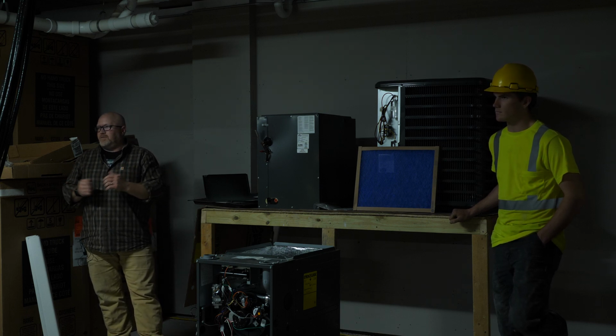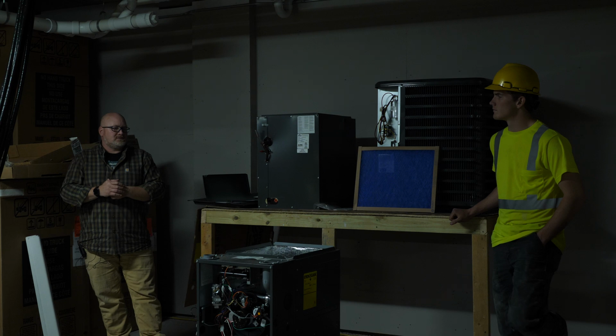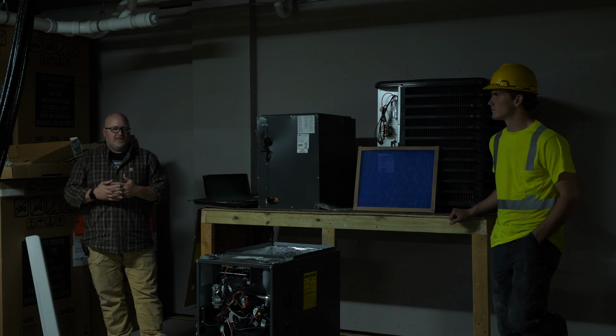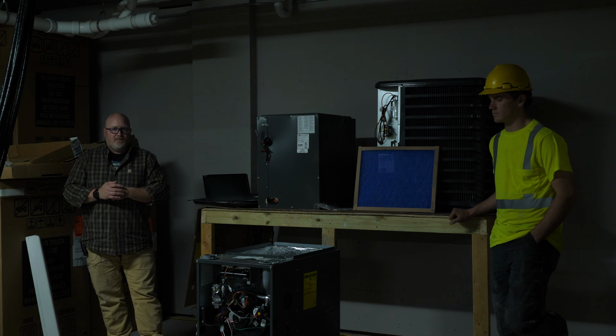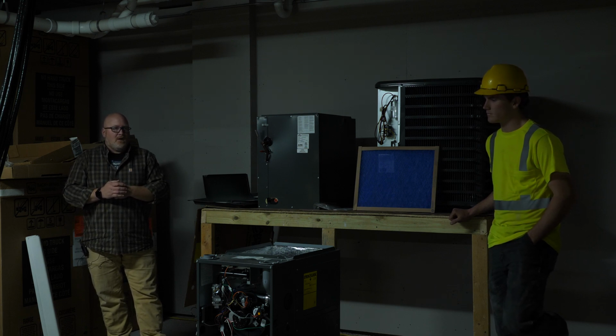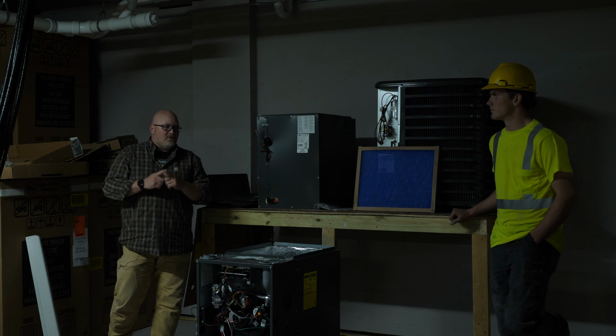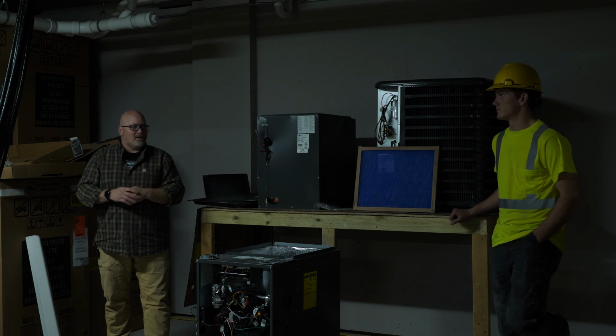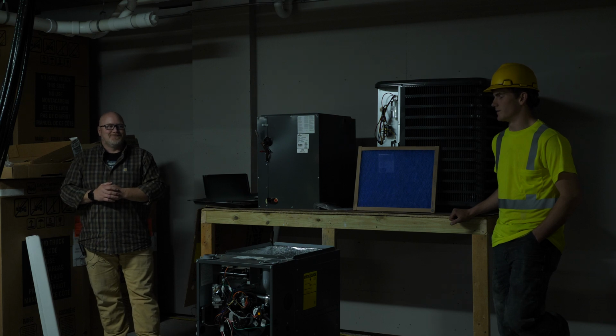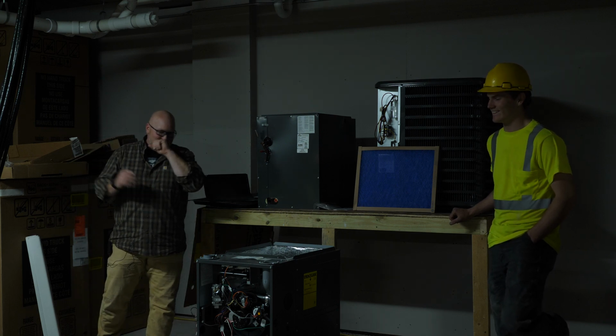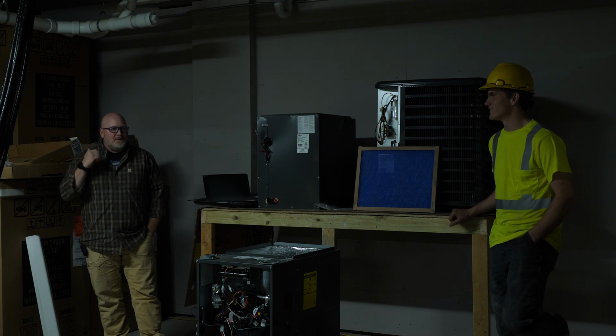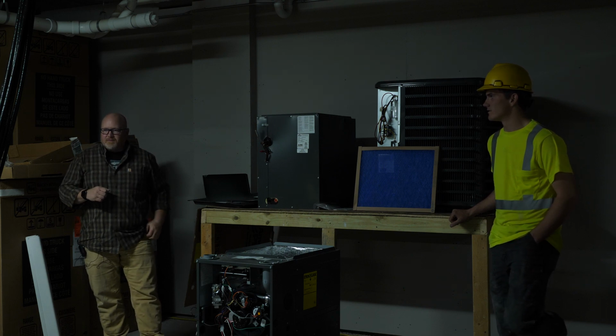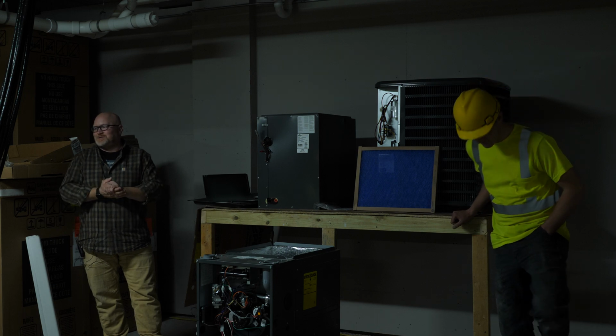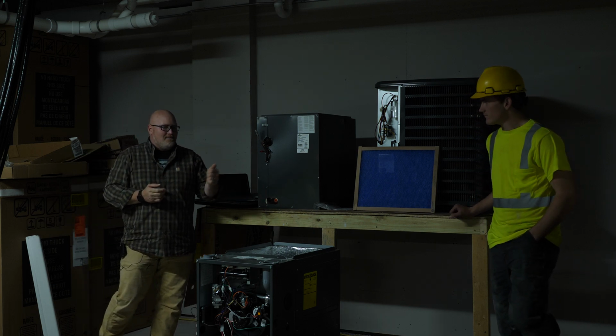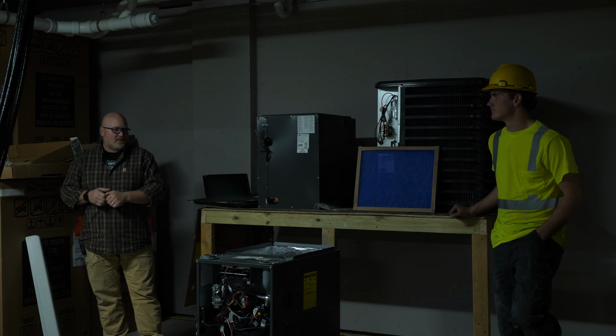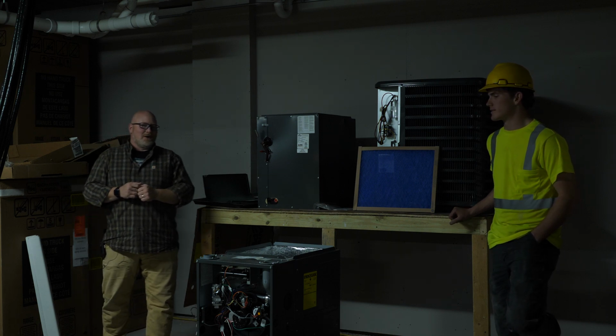I'm a big fan of the mastic, not so much the tape, just because tape often really comes down to the quality of how the tape was applied, and tape can often also dry out sometimes. That's why in the HVAC trade we never ever use what? It's gray, comes on a roll. Duct tape. And I get a kick out of it because when I go to the Home Depot here, in the ductwork section is the biggest variety of duct tape you've ever seen. And I will reiterate again, it is against code to use duct tape on ductwork. So don't ever put duct tape on your system.